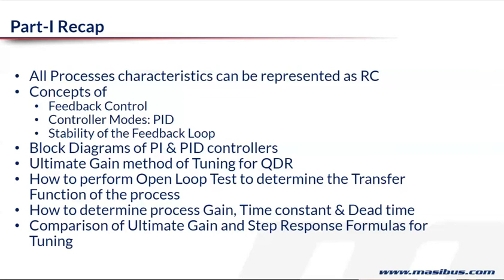And we also talked of the stability of a feedback loop. Now, if you do not set your PID parameters properly, the loop itself can become unstable and you could see a lot of oscillations. So sometimes if the integral time is too short, or you've not configured direct or reverse mode properly, all this can lead to instability or stability of the loop.